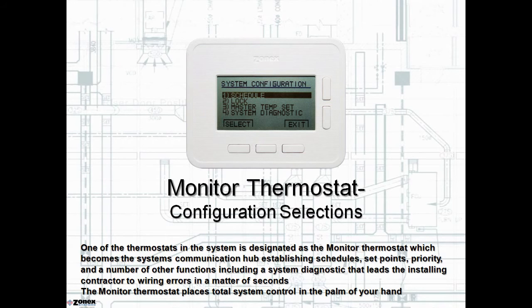One thermostat is selected as the monitor thermostat. This becomes the nerve center for the system where all control decisions are made and executed. On this screen, select schedules for one or each thermostat in the system. Any thermostat can be locked from the monitor, globally or individually, and all stat temperatures can be individually set, both occupied and unoccupied heating and cooling set points. This is a real time saver for the installing contractor, setting up each thermostat as well as system operation with the monitor thermostat located right in the palm of his hand.